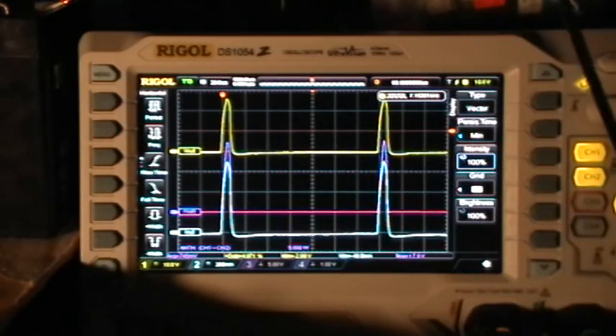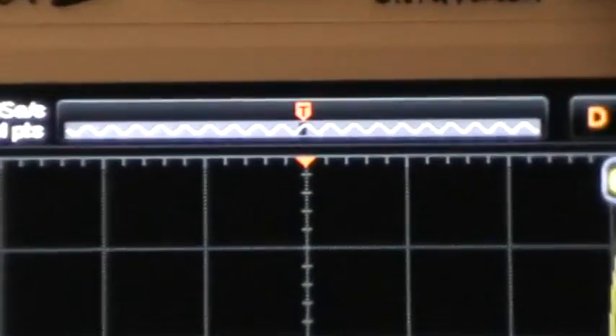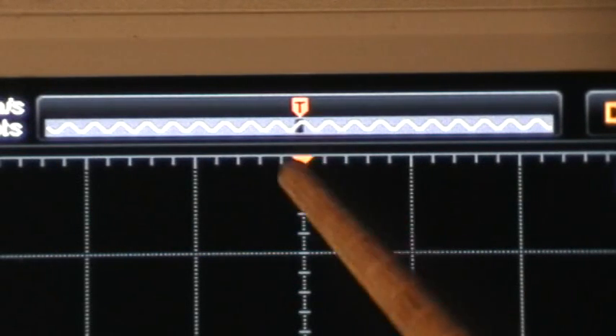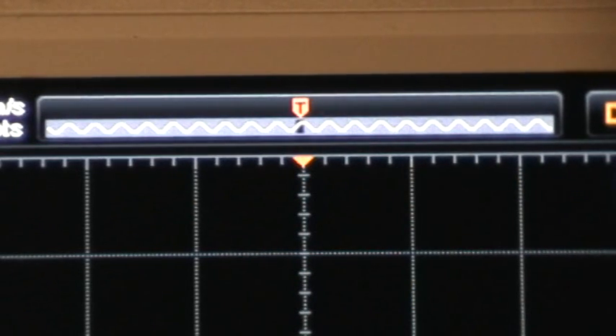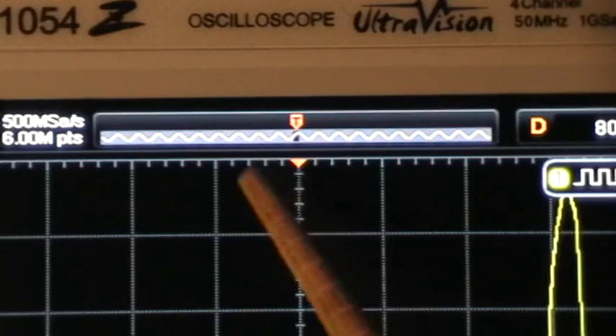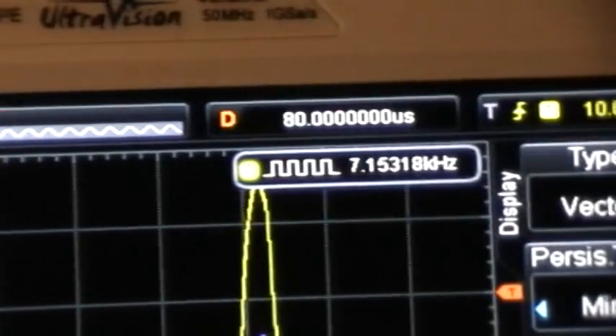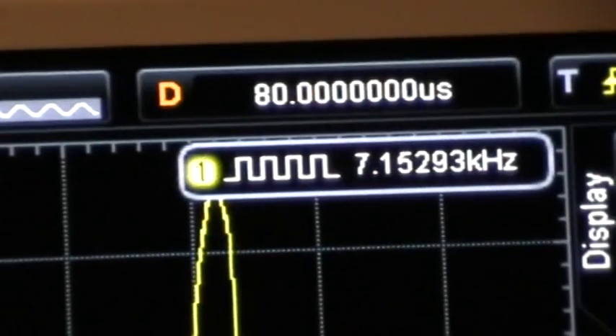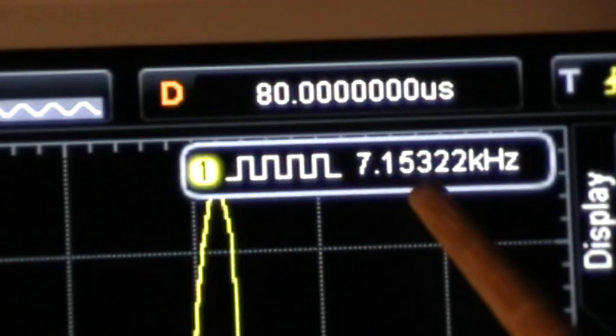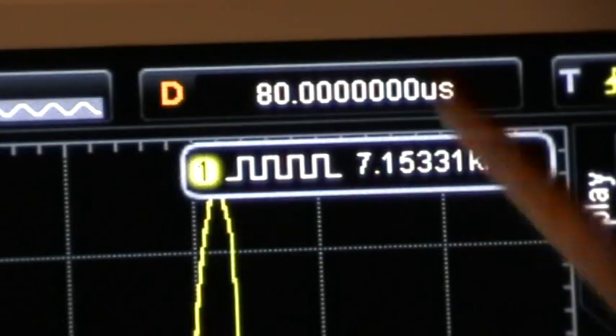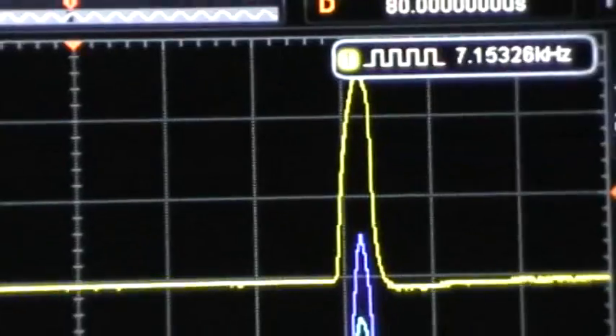This little top bar here shows the entire memory buffer and also the portion — that little portion right there — that is what is on the screen display. You can see that the whole memory right now is holding a lot more information than just what we're seeing on the screen. The Rigol has a hardware frequency counter, and that's showing the frequency calculated from the entire memory buffer. But that's the only measurement that is calculated from the entire memory buffer.